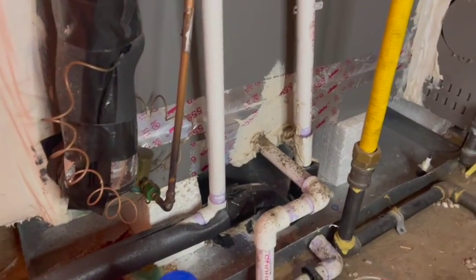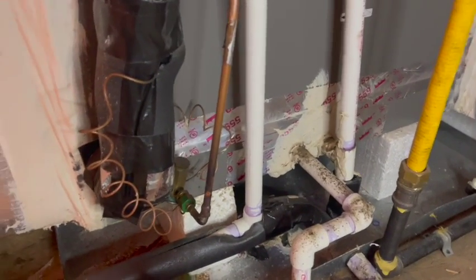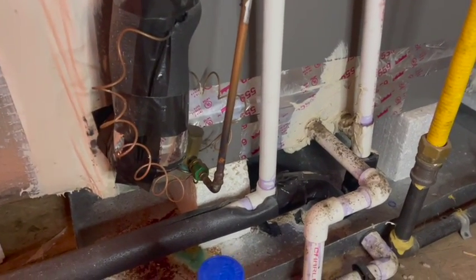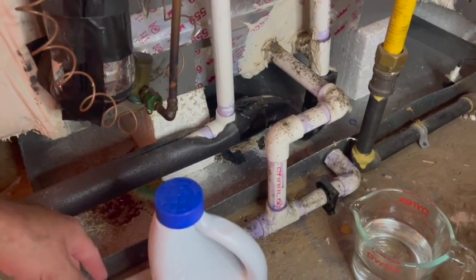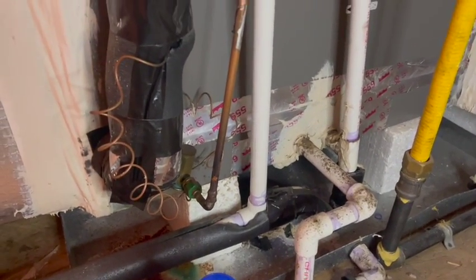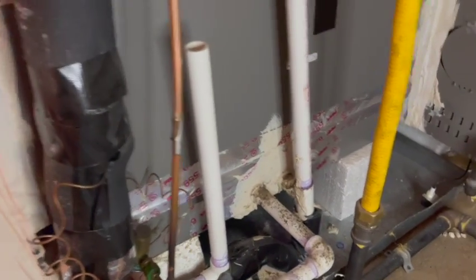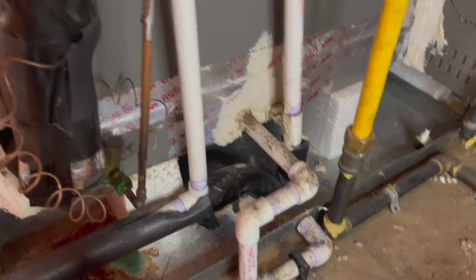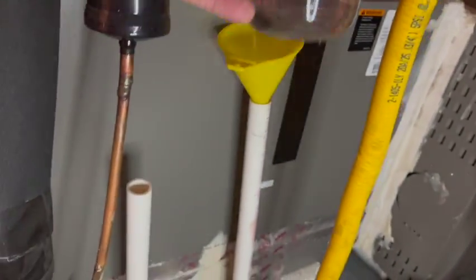When you see water coming out of that secondary pipe on the outside of the house, it's in a conspicuous location because that means your primary is clogged and you're having water collect, hopefully in your pan, or it's not getting into the house. So first, let's take a look at putting the Clorox or the bleach solution into the primary.